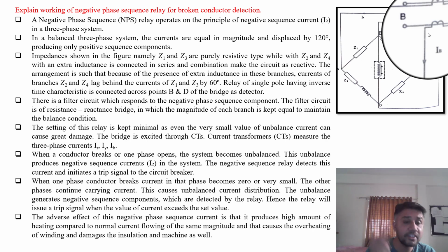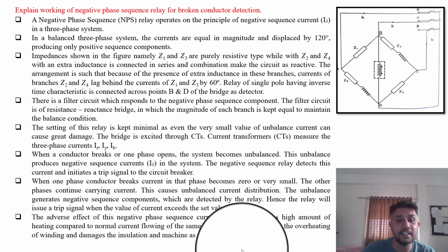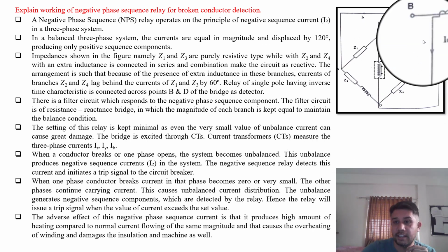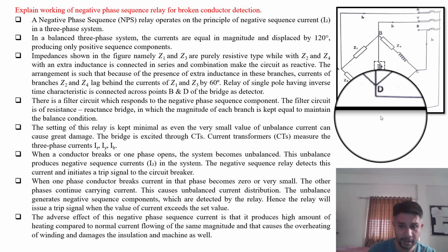Now when one phase conductor breaks, the current in that phase becomes zero or very small. The other phases continue carrying current. This causes an unbalanced current distribution. The unbalance generates the negative sequence component, which is detected by this relay, this coil. Hence, the relay will issue a trip signal when the value of the current exceeds the preset value.